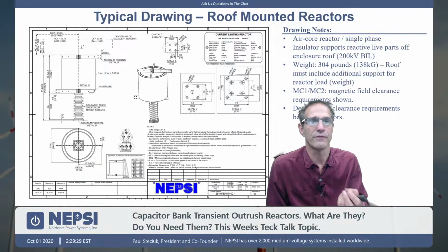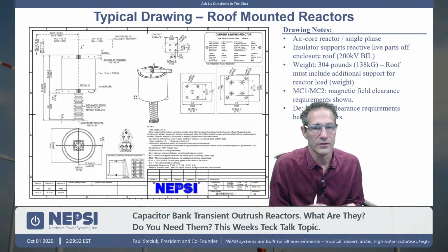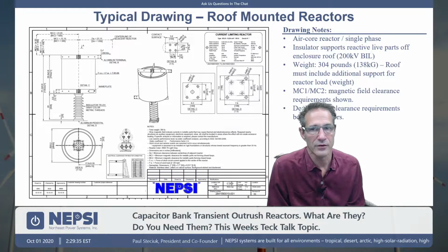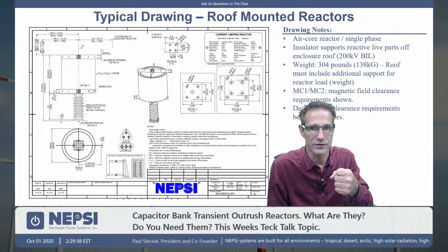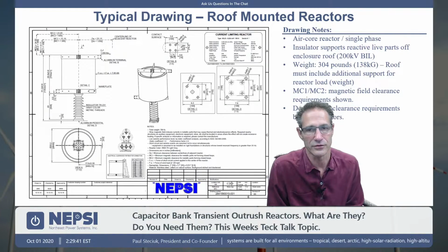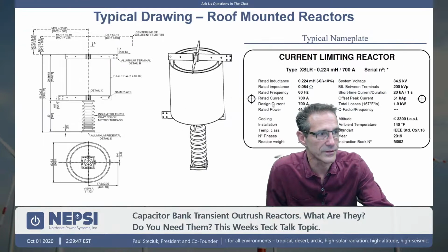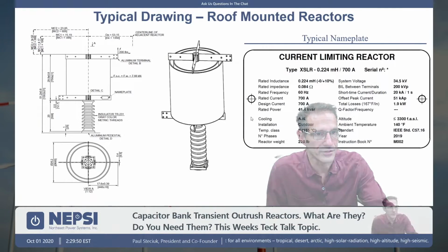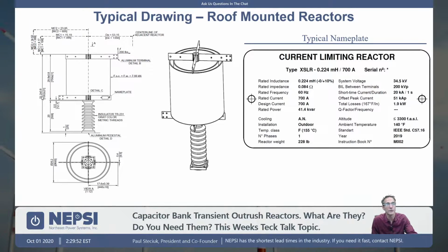So when we put it on a roof, we have to reinforce the roof, not only for the snow load, but also for the weight of the reactor, and then also the torque that might be pushed onto the reactor from the cables or the buswork that is connected to the reactors. So these are all things that we have to consider. Just quickly, as dimensional, we're dealing here with 51 inches tall. So they're pretty tall reactors. We typically like to do an increased impulse level up on top because of snow and because of the possibility of bird contact and things like that. We're typically trying to bump up at least one BIL level on top as a standard to improve reliability.